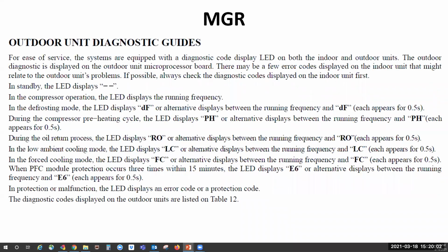We're going to jump in here to the MGR units and for diagnostics. On the high wall systems, you can see they have a display, and a lot of times the display is just telling you what it's doing, like DF is defrost, preheat, oil return, things like that. So it is just telling you what it's doing, not necessarily that it has a fault code.